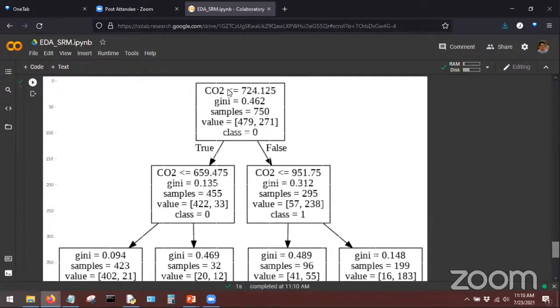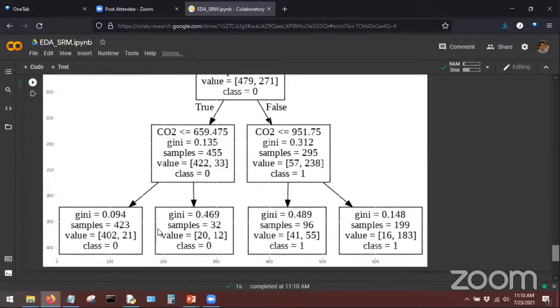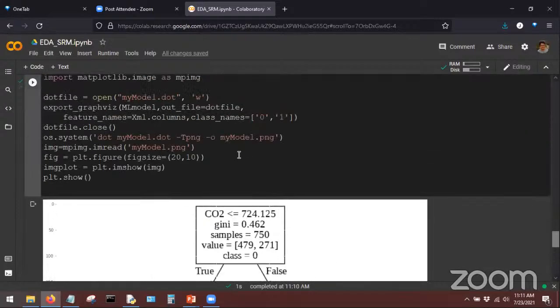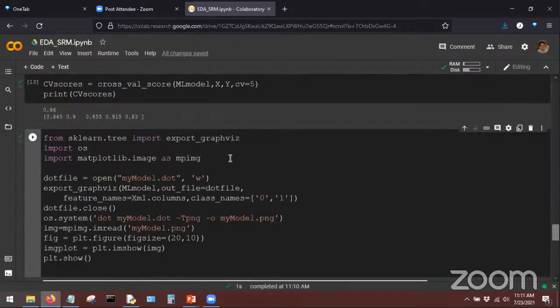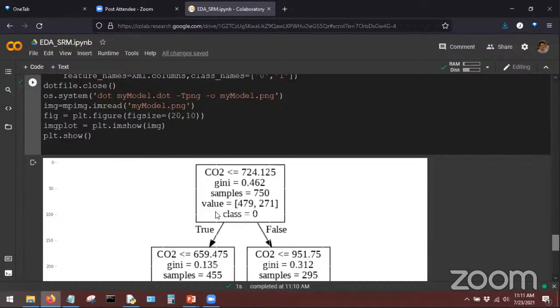So you can clearly say that when CO2 level is less than 724, it is not occupied. When CO2 level is greater than 724, it is occupied. That's all - you can easily put this logic in your embedded board and test it, assuming the rooms are identical, since this data was collected for one room. The logic we learned here, we apply to an embedded board and test it on another room, assuming both are identical.